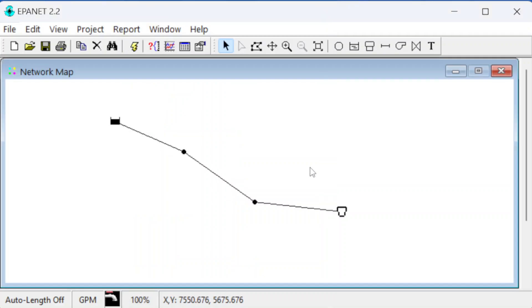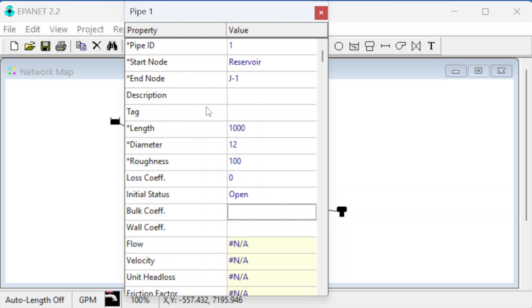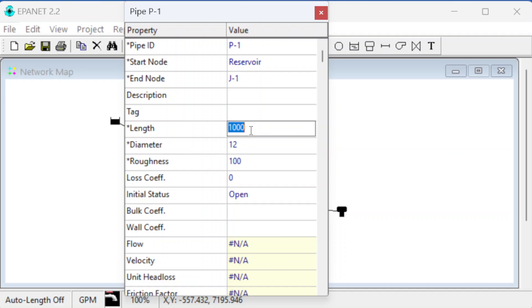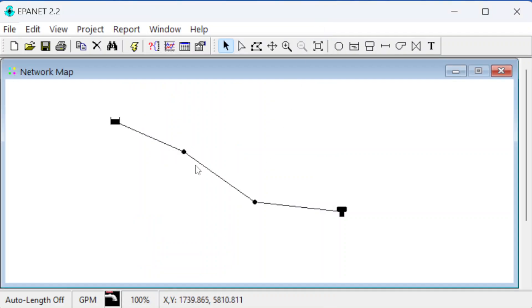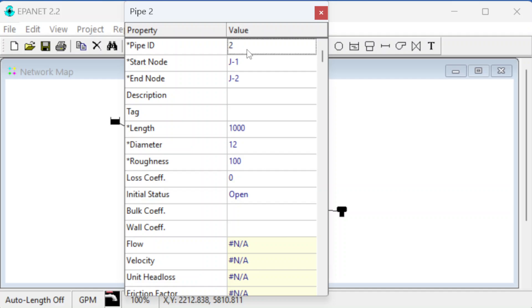That's everything for the tank. Now for the pipes. Pipe P1 goes from the reservoir to J1 — we'll rename it P1. It has a length of 300, a diameter of 6 inches, and it's cast iron with a Hazen-Williams C value roughness of 100. That should be everything needed for that pipe.